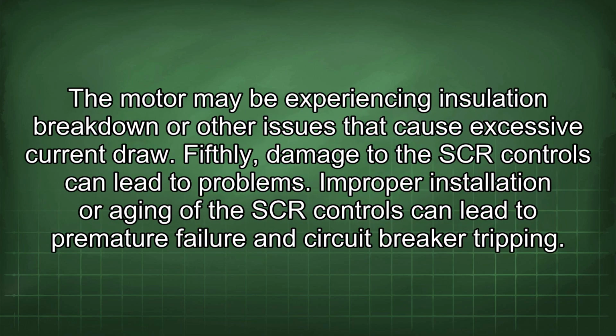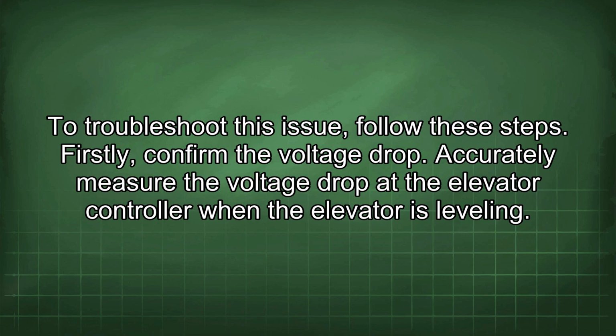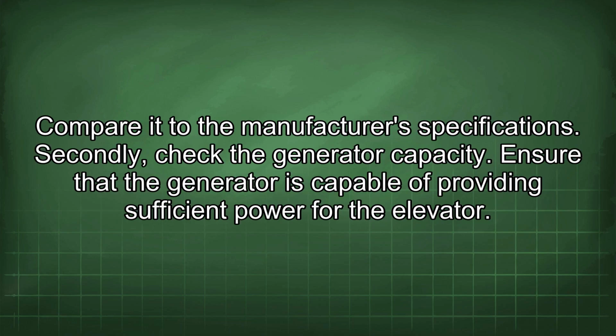The motor may be experiencing insulation breakdown or other issues that cause excessive current draw. Fifthly, damage to the SCR controls can lead to problems. Improper installation or aging of the SCR controls can lead to premature failure and circuit breaker tripping. To troubleshoot this issue, follow these steps. Firstly, confirm the voltage drop. Accurately measure the voltage drop at the elevator controller when the elevator is leveling. Compare it to the manufacturer's specifications.